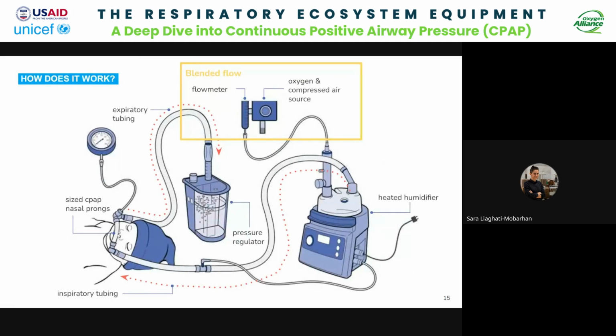So as I was saying, the blended flow is typically made up of a flow meter or of some type of oxygen source and some type of air source. So typically ambient air is used, it can be filtered. And then for the oxygen source, this depends on the product, depends on the type of CPAP device that you have, but it can typically be provided through any oxygen source. So whether that's a PSA plant that's providing walled oxygen, a tank that's been purchased, or an oxygen concentrator.